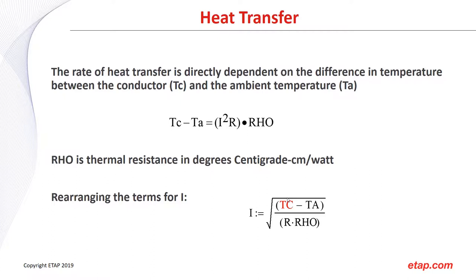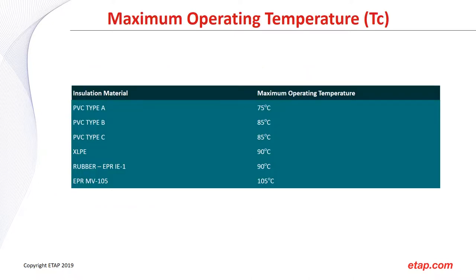The rate of heat transfer is directly dependent on the temperature difference between the conductor TC and the ambient temperature TA. A brief representation of the formula is: I²R times the soil thermal resistivity (rho). Solving for current (I), we rearrange the terms as a function of I. This is a basic representation of how heat transfer is handled for hand calculations.